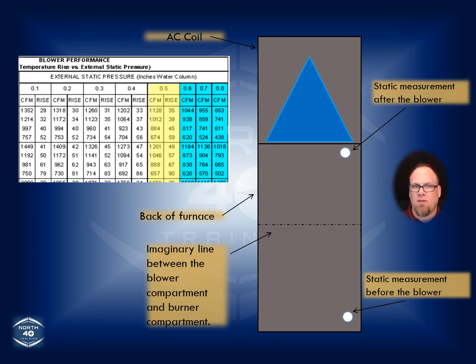on the right-hand side of center. You could actually go up to 0.8 inches of static on this, as well as most other manufacturers that have multi-speed blowers, and still be within a verifiable range. And the idea here is to check the static before the blower and after the blower, add those values together as raw numbers, take them over to this chart, and plot those across the top of the chart. Okay, so we've got 0.5 inches of static and I'm on low speed. Well, I'd have 674 CFM going through that air conditioner and furnace at that time. So that's the kind of value that we're looking at there, and we're going to explain this a little bit more, but really this is, in a general sense, some of the baseline information that you've got to know in order to properly set up your furnace.